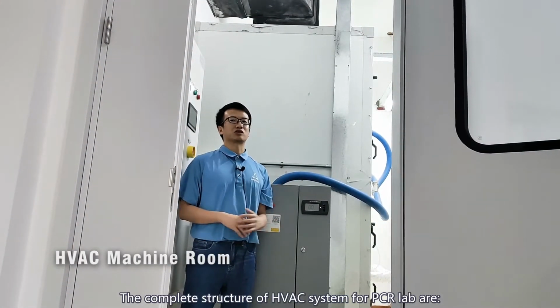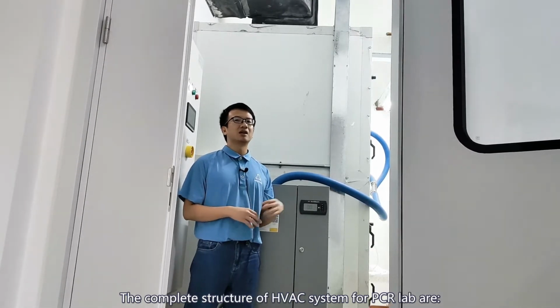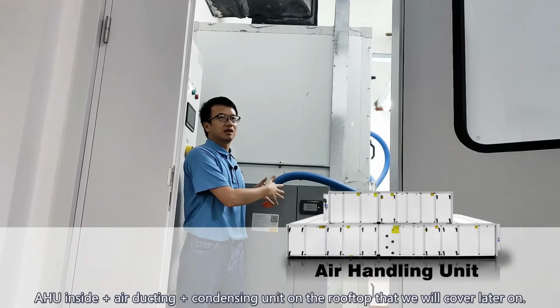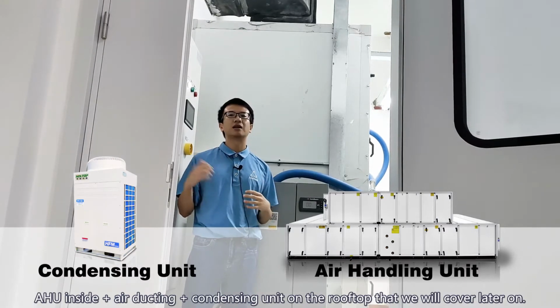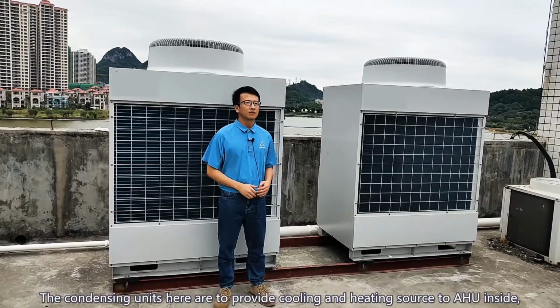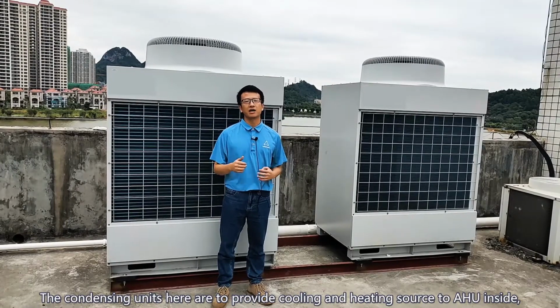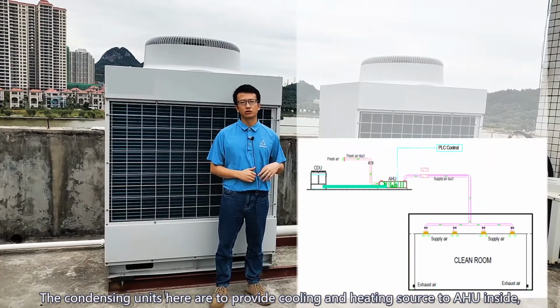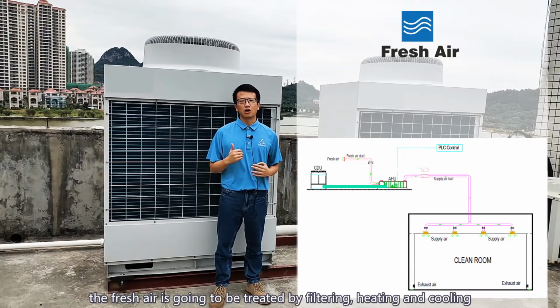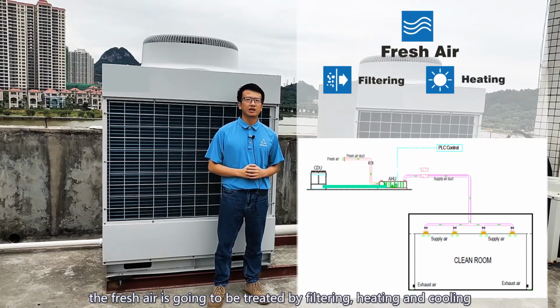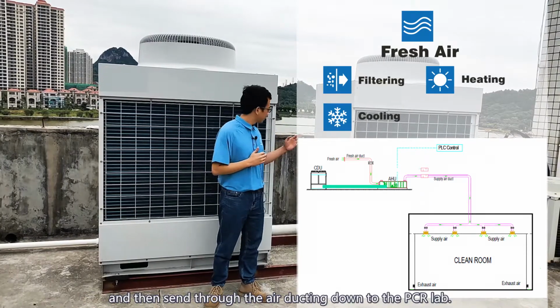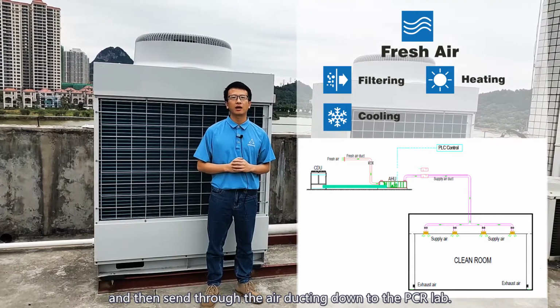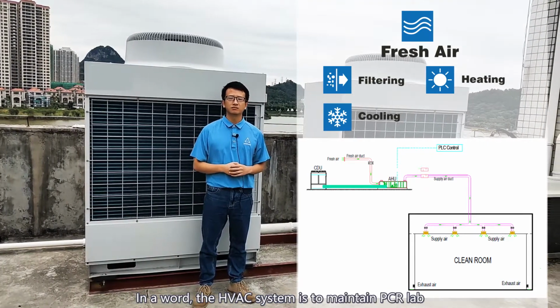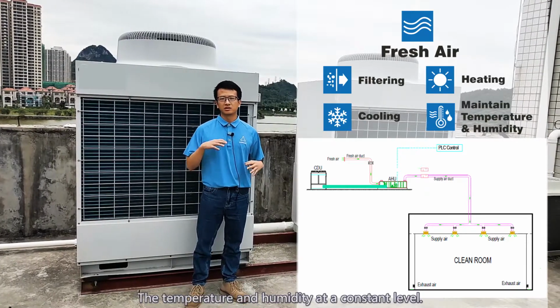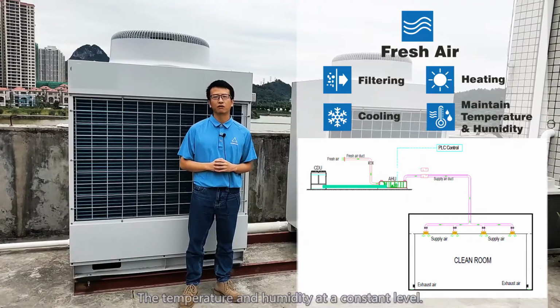The complete structure of the HVAC system for the PCR lab is the AHU here inside, plus the air ductings and another condensing unit on the rooftop that we will cover later on. The condensing units here provide the cooling and heating source to the AHU inside. The fresh air is treated by filtering, heating and cooling, and then sent through the air ductings all the way down to the PCR lab. In a word, the HVAC system maintains the PCR lab's temperature and humidity at a constant level.